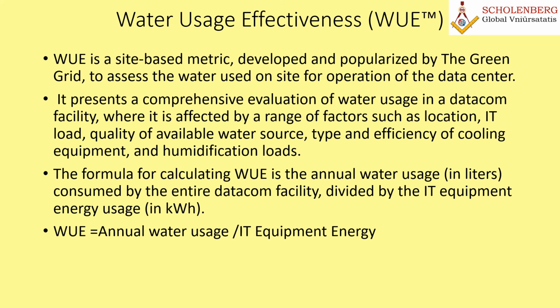The formula for calculating WUE is annual water usage in liters consumed by the entire datacom facility divided by the IT equipment energy usage in kilowatt hour. So WUE is equal to annual water usage in liters divided by IT equipment energy consumed in kilowatt hour. So this is a very important factor which you will need to ask about or consider in your proposal. Based on that, you can impress the client that you know about the WUE, and this will make your case very strong in front of the client.